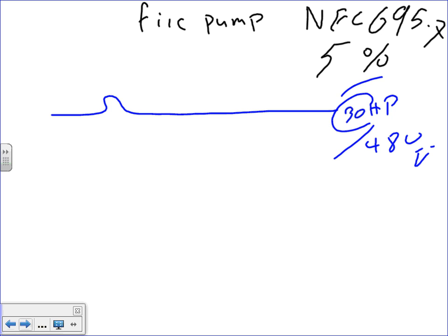There's dip and drop. Dip, when you start momentarily for 10 seconds, you can dip the voltage down to 15%, just for 10 seconds. Drop means constantly. Constantly, the voltage can be 5% less, no problem. This is voltage drop. 695.7 says the voltage at the line terminal of a controller when starting, the locked rotor, must not drop more than 15% under motor starting conditions.